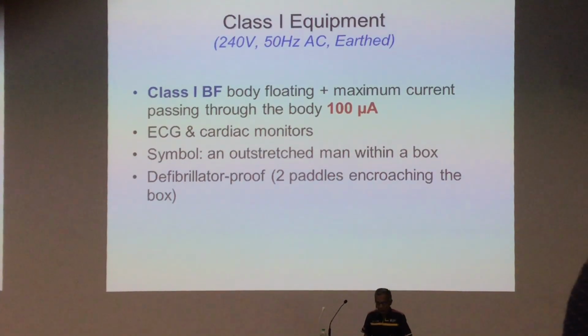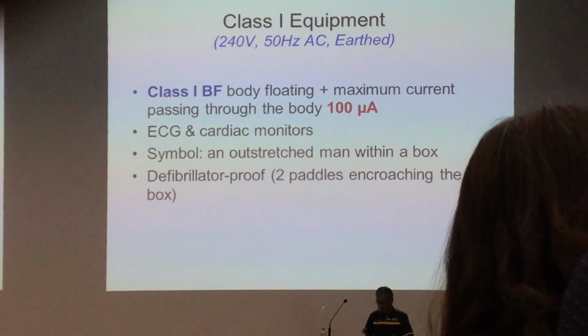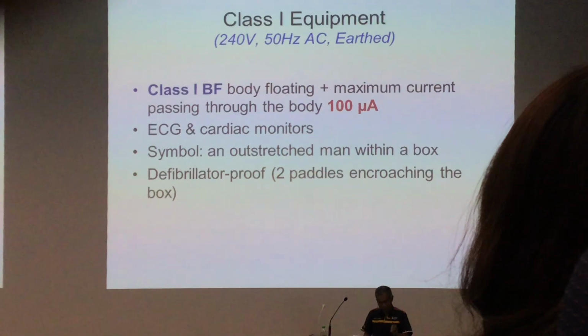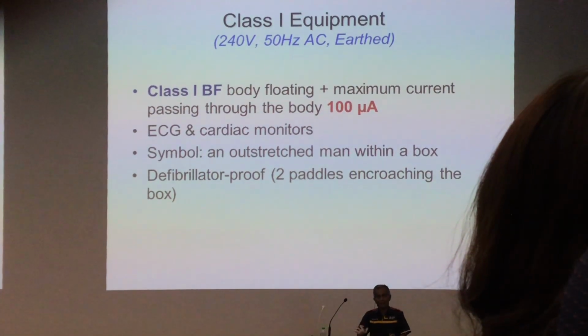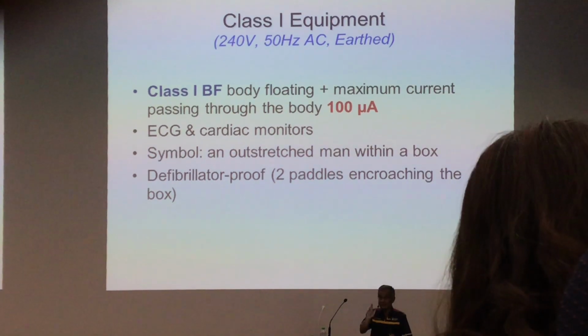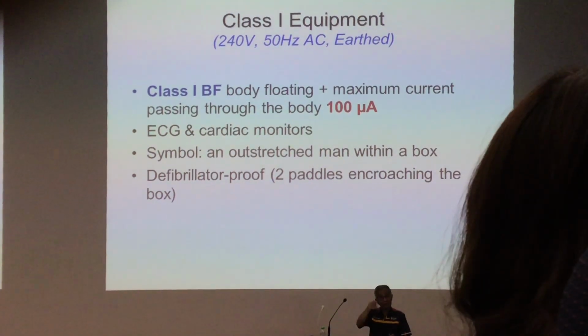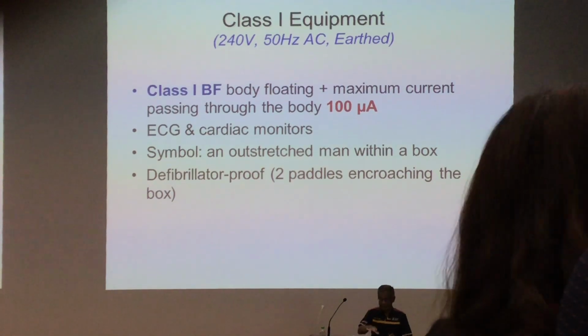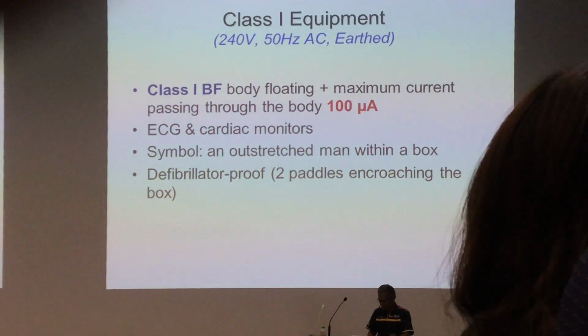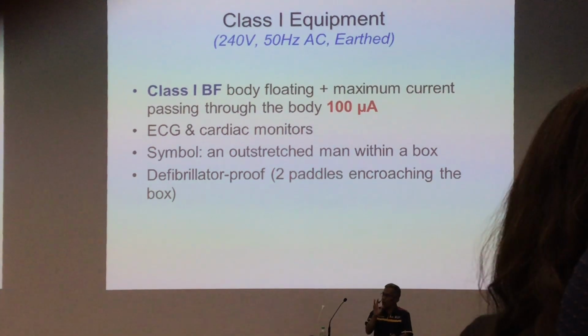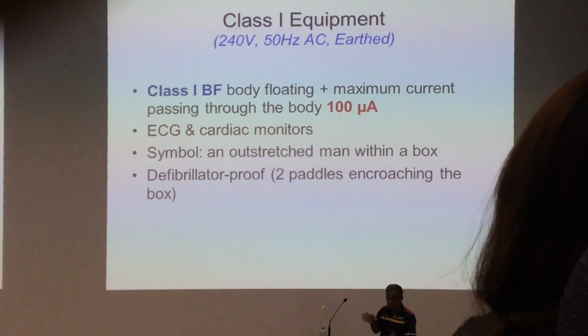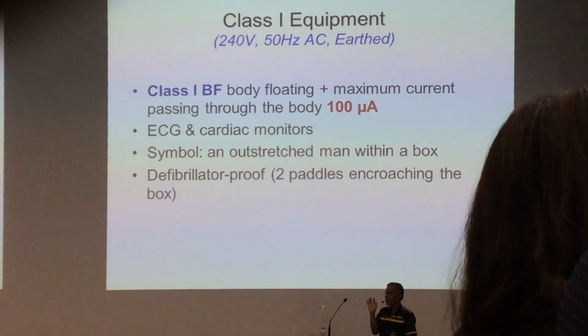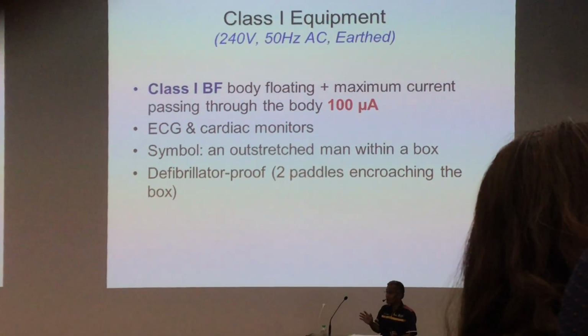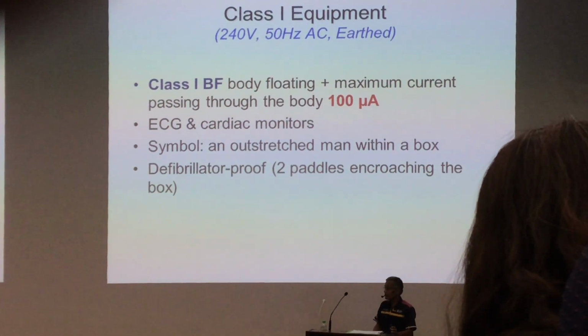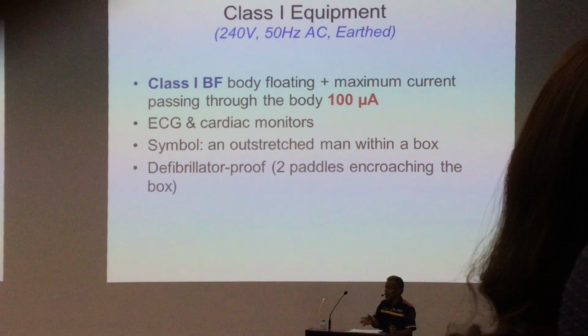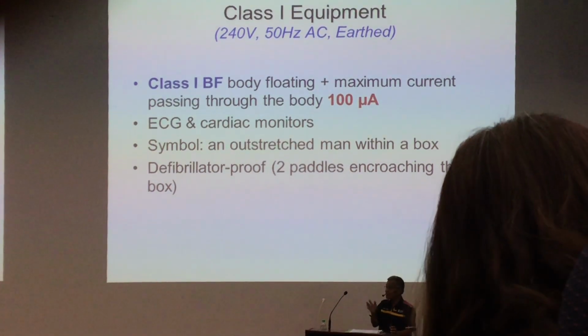The other one, class 1, but it is BF. This is CF, this is BF, also class 1. But the current is slightly higher, 100 microamp. Both currents, 10 microamp and 100 microamp, can cause VF if they contact the heart directly. So this is just a classification, but you don't need to worry very much. But if you know, all cardiac procedures must be done in class 1. That's it. It's more than enough. Any cardiac procedure, you must do it in a dedicated OT where the electrical supply belongs to class 1.